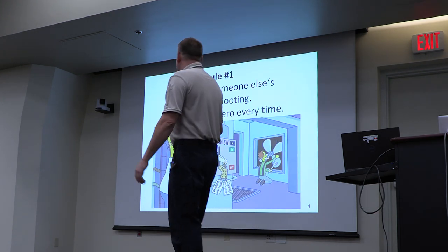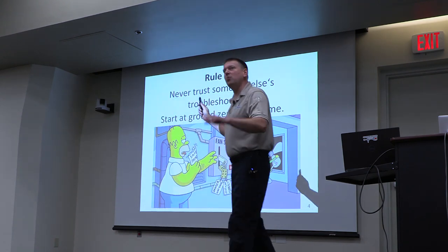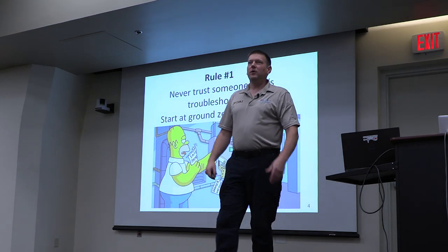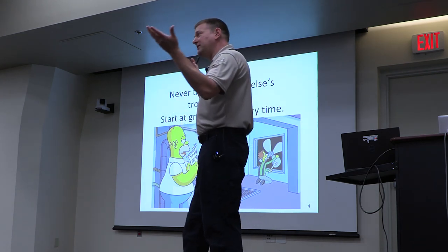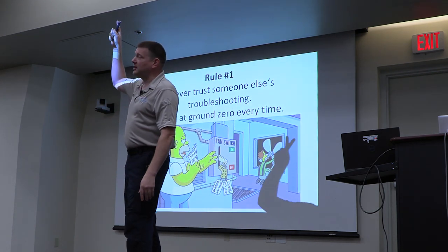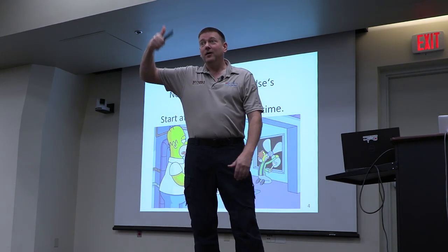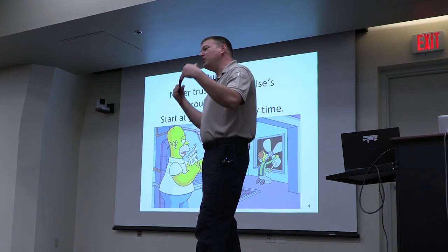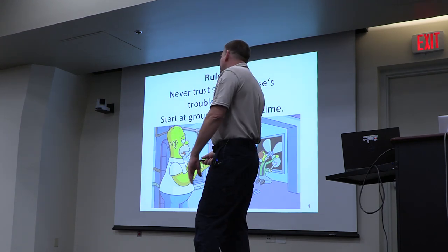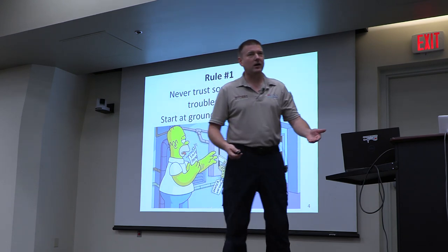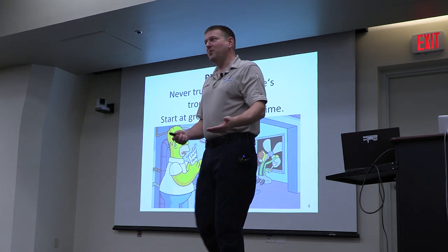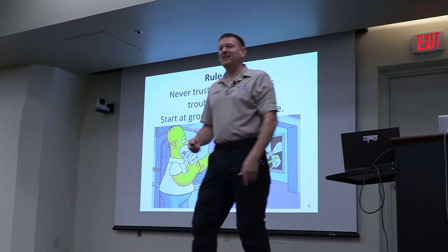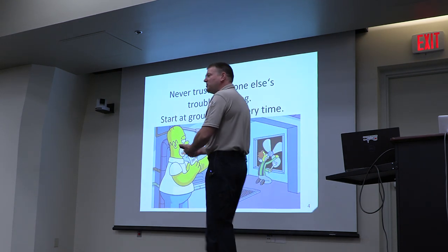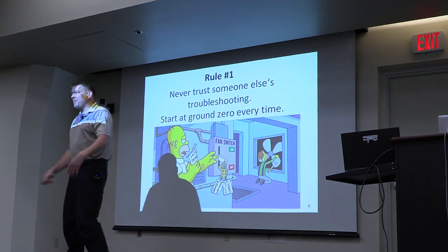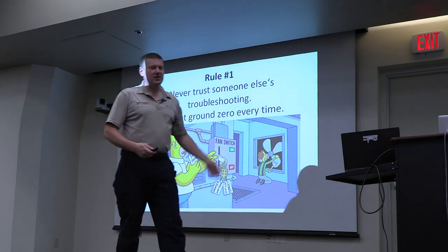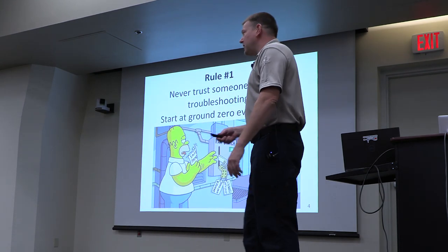But the other reason is you always want to start at ground zero, because you want to verify it's safe for you. So if you go above ceiling to work on some lights - depends on the lights, these ones here do not operate at 220 volts, higher guys - when you go to work on something, you want to make sure it's safe for you, which means you have to verify it from square one. If somebody says they locked out a breaker, go and make sure the breaker's locked out. Take out your multimeter and check it to make sure it's de-energized. Same thing goes with spring suspension, loads, pneumatic, steam, all the above. We have some of the most hazardous environments to work in out of almost any career field. Make sure it's safe for you.